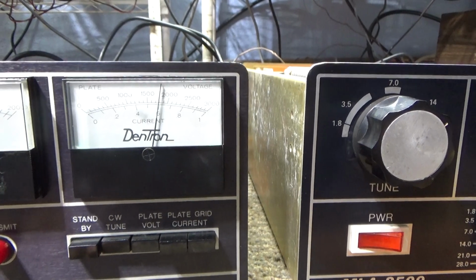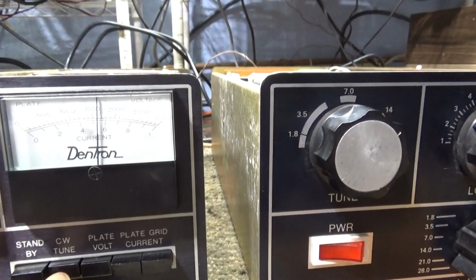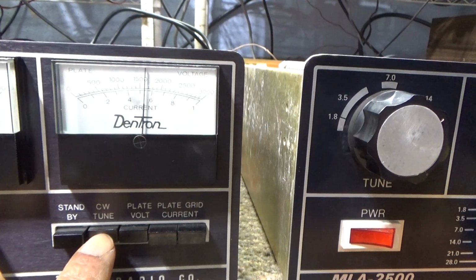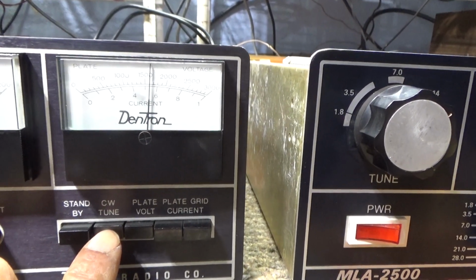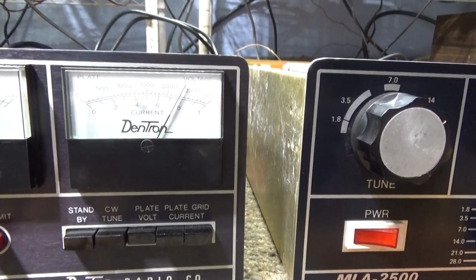That's that poor man's self start, or soft start. It'll start on the low voltage tap at 1800, and then when the time delay kicks in after 90 seconds, it'll jump up to the high voltage.